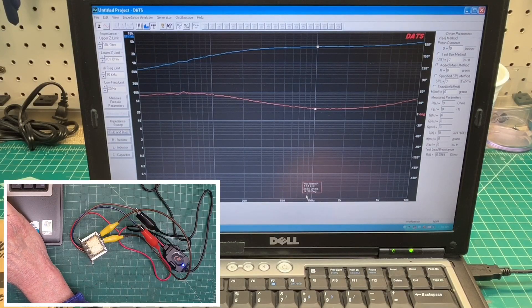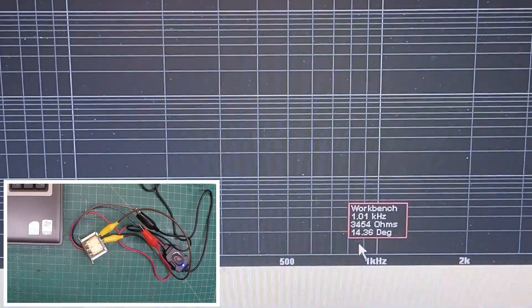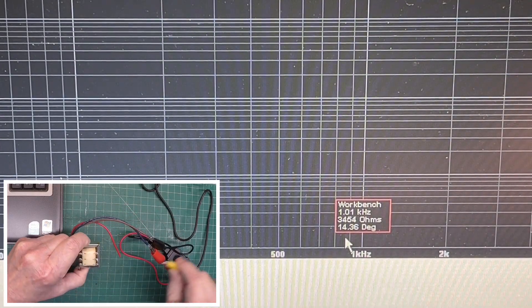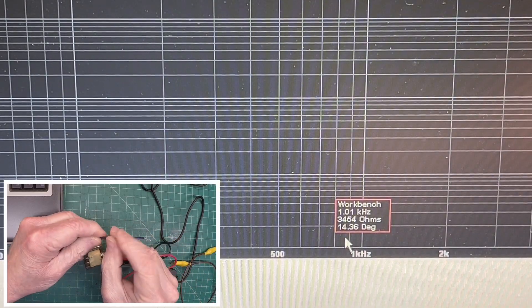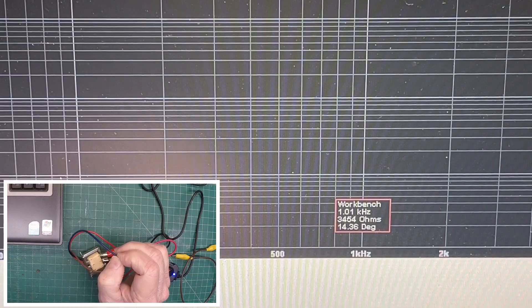If it's showing up — what, 3454? Let me zoom in on that just a bit. So we can take note of that number. I'll remove the short from the secondary, just move the leads back over to the 1 and 2 position on the transformer on the secondary side. And in this case I'll short the primary and repeat the impedance sweep.